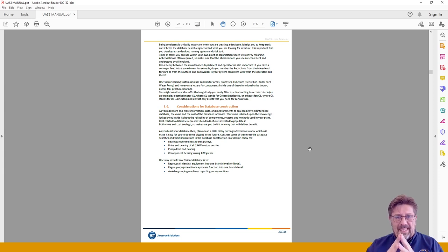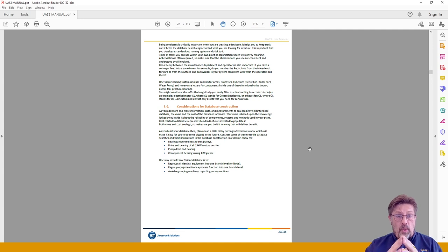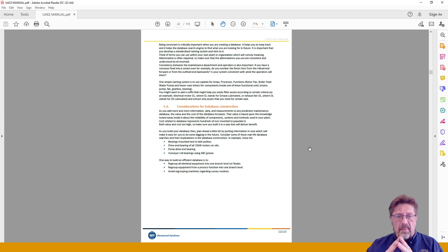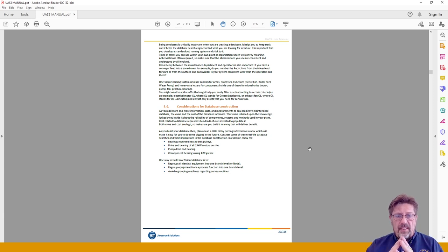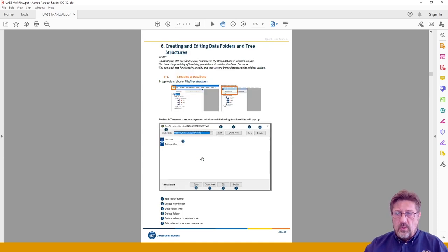For example, if you want to analyze what's going on with the recirculation pumps in a certain group, you also want to see both the leading pump and the backup pump and compare them, maybe to decide to switch to the backup pump. For that decision, you need the assets grouped in a logical way reflecting how they work. But we also know that when a person goes to collect data, those two pumps will never be working at the same time, so they should not be in the same work order. So instead of building your tree structure in a way that's hard for you, just do it in a logical way — the way you want to see the data. How the data will be collected is one of the chapters in this training, and we can make it perfectly suited for the field technician. Build your database in a way you want to manage your assets, understand them, compare them, and make decisions based on multiple data.